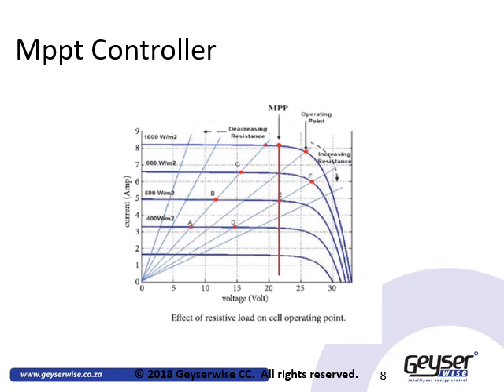In other words, in order to achieve the full potential of a water heater with a fixed resistive heating element from your PV array, you would have to fit your water heater with approximately 4 to 5 different heating elements with different resistances and a complicated switching mechanism that would switch between them in different weather conditions.